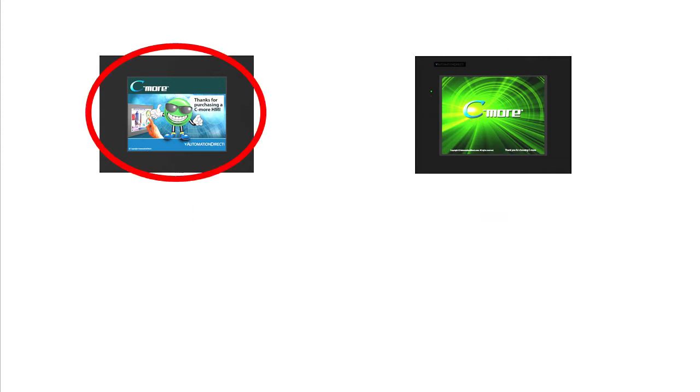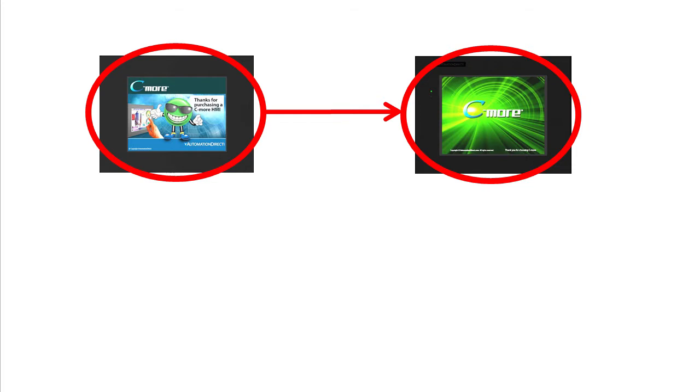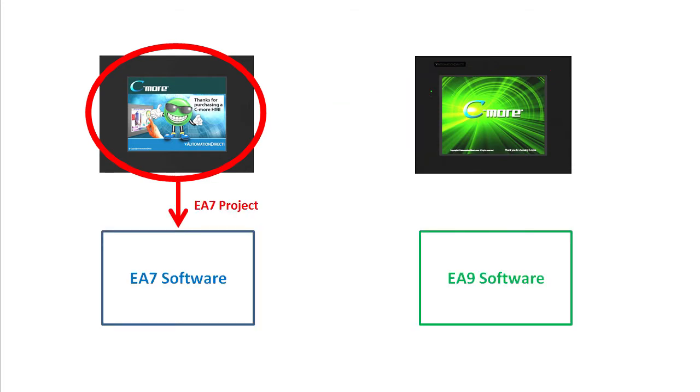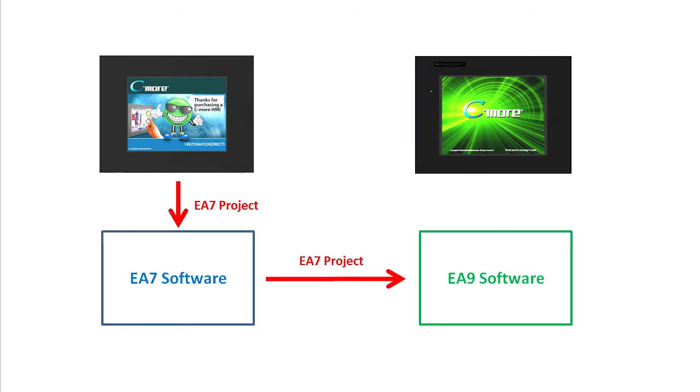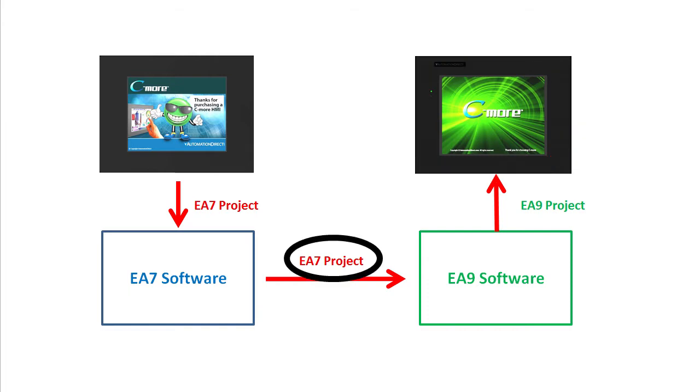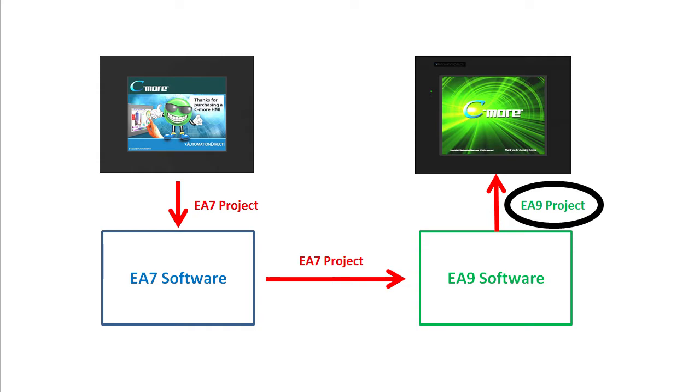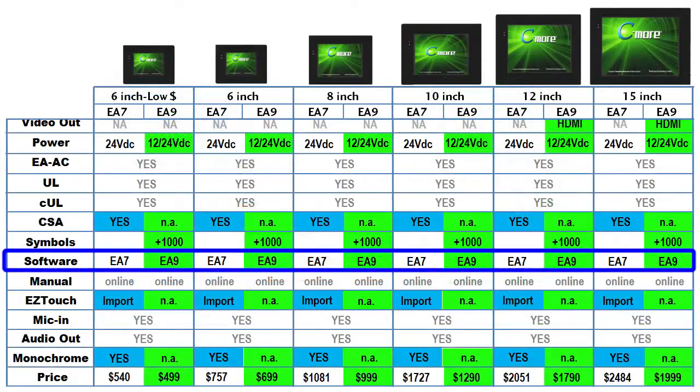So to get this project over here, you need to read the project into the EA7 software, then open that in the EA9 software which you would then use to transfer the project to the new panel. The EA9 software opens the EA7 project just like any other – it automatically makes any necessary conversions and issues any warnings or reminders that you need to be aware of. Easy.